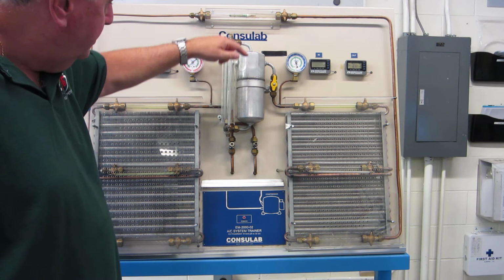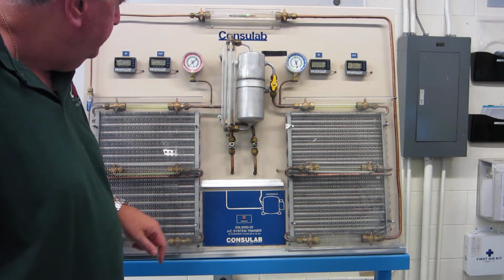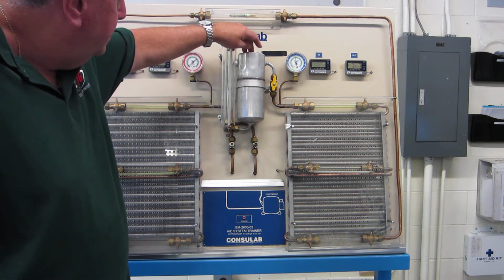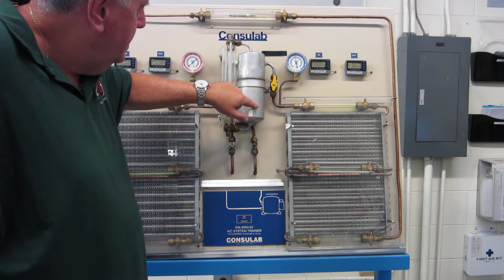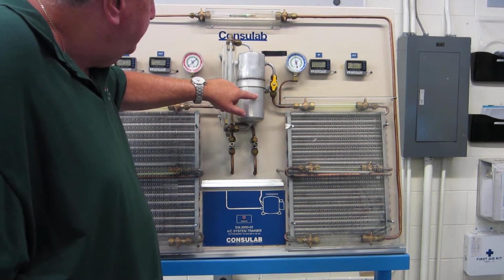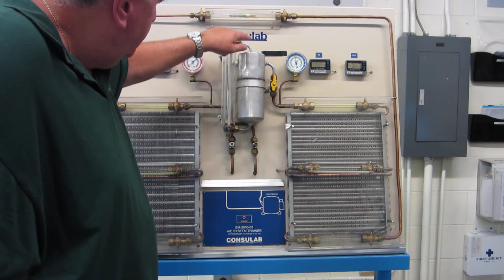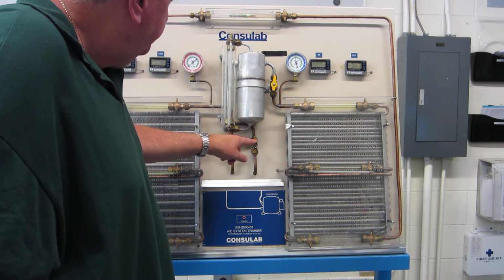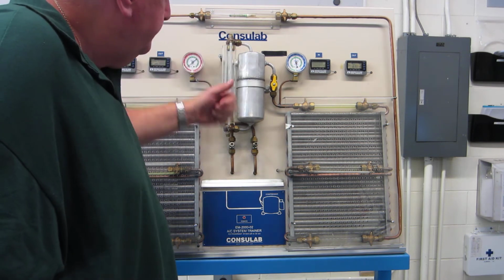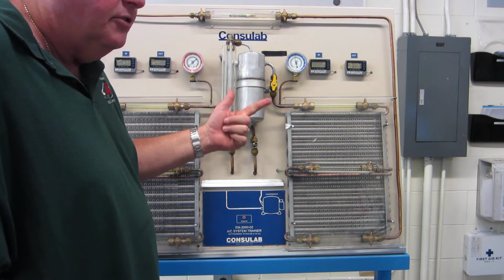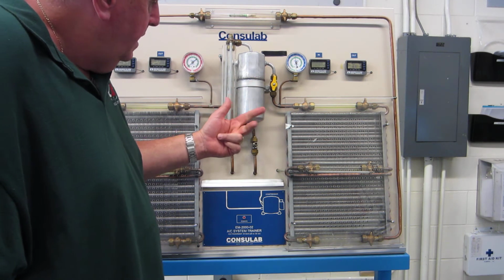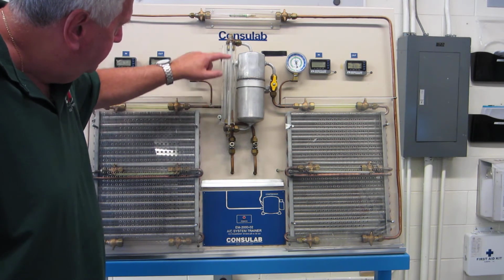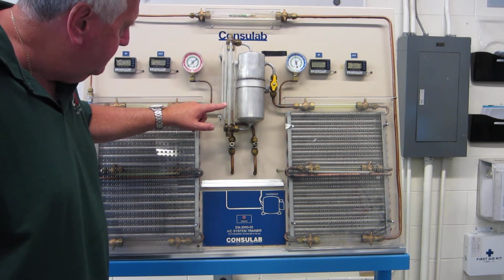So there is only vapor headed off to the compressor. Remember how this works? Liquid would now come in and drop to the bottom, and as this heats up, the gas would rise up, and we now would pick up the vapor and head off to the compressor. Just like the receiver dryer, it's going to filter, it's going to remove the moisture, the desiccant, and it's a storage container. So you'll notice a sight glass on the side when you have a look at this board, and you'll actually be able to see the amount of refrigerant flow.